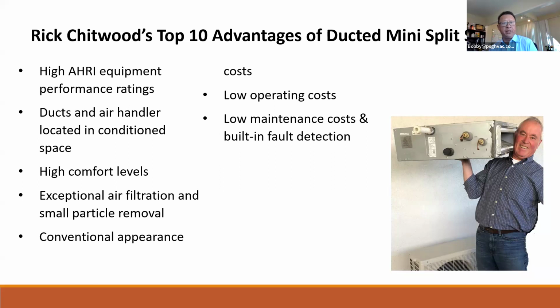Back to the condensing unit, very low operating cost because of the inverter. We are not overshooting, we're matching the load. We are just trying to get exactly where the load is and stay there, and low maintenance cost and built-in fault detection. So for instance, with this ducted unit in California, in a lot of cases you're going to have a secondary drain pan. We can put a sensor in the drain pan, and it will knock down the unit in case it floods. So the unit will turn off. So a lot of built-in detection with these advanced units.